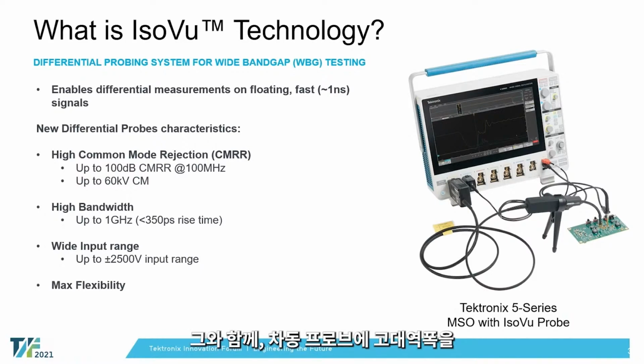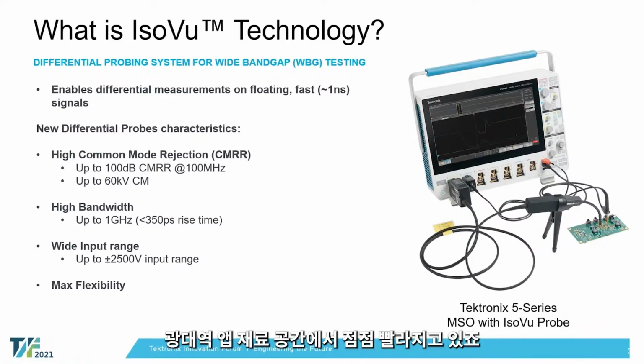Coupling along with that, we keep a very high bandwidth with our differential probe. For something as high dynamic range as 2500V, you often don't see bandwidths up above, say, a couple hundred megahertz or so. With IsoVu, we're able to achieve a gigahertz of bandwidth, and where that really allows for some interesting measurements, again, in the wide bandgap space, is being able to really focus in on the DVDT and potentially DIDT type of measurements that are becoming faster and faster in the space of wide bandgap materials.